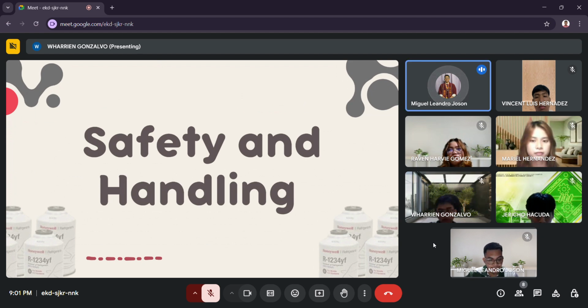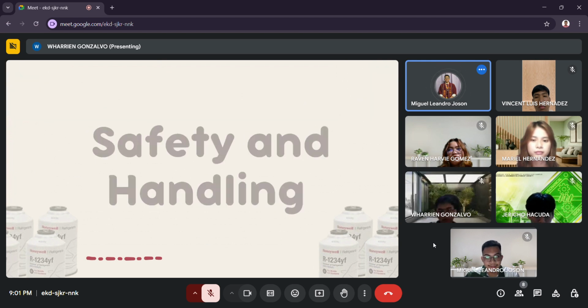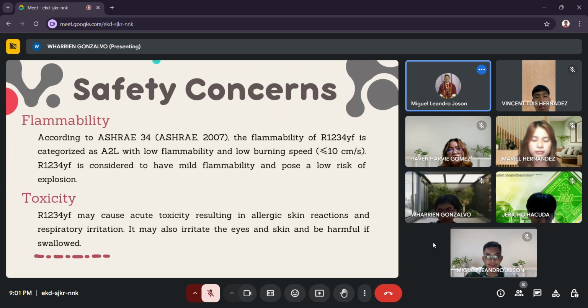For the safety and handling, we first have the safety concerns. Next slide. Flammability. According to ASHRAE 34, or ASHRAE 2007, the flammability of R1234yf is categorized as A2L, with low flammability and low burning speed. R1234yf is considered to have mild flammability and pose a low risk of explosion.